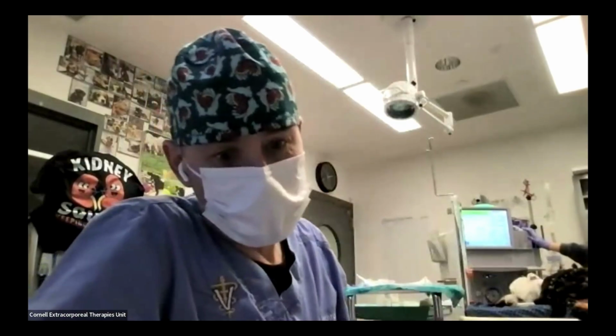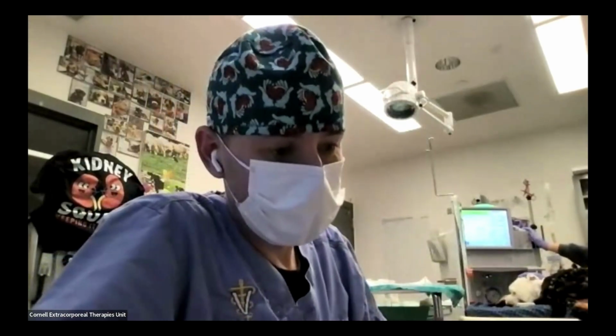Erica, when you set yours up, did you connect that venous pressure side too? Yeah. We try to do the arterial pressure monitoring by, like you said, adding an extension set with a pressure transducer. And it definitely helps with access alarms, like it will stop the pump. And yeah, I have hooked up the venous side because I don't think you can run it without a pressure transducer hooked up on the venous side. It'll just keep giving you TMP alarms without it being hooked up.